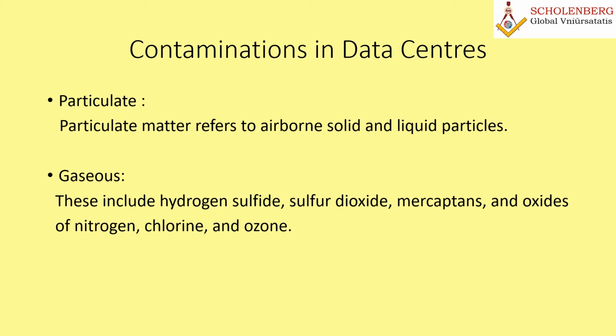Airborne dust contaminants can be detected from detailed visual inspection of the filters in air handling systems or standalone units. The presence of gaseous contaminants may require seasonal or periodic monitoring and measurement through the use of copper and silver coupon testing in datacom rooms.